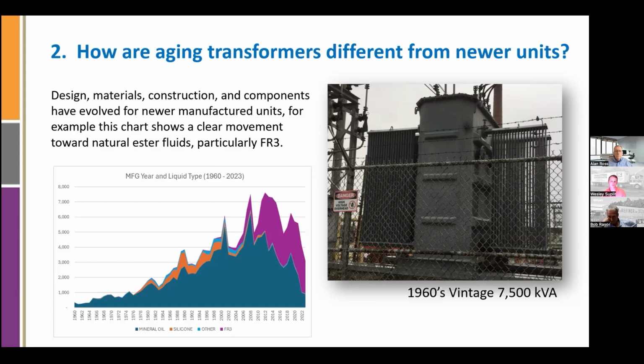And that is taking a portion of the mineral oil over the last 20 years on newly installed and newly manufactured pieces of equipment. And again, the same kind of ideas for why FR3 is popular. It's got a higher fire and flash point. It's more resilient to moisture. It can hold up in a lot of operating conditions. So there's a lot of benefits there. But the point is that I just want to show how aging units have original components, more or less. Original gauges, original bushings, original gaskets, original fluids, original paper, even paper that might not be thermally upgraded.